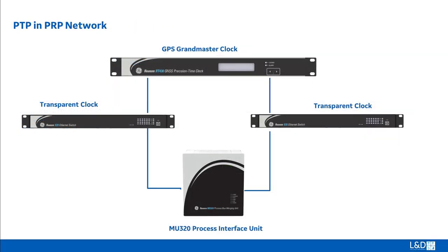Scenarios where using PTP in a PRP network is required are rapidly increasing, as these 2 protocols meet all the benefits and economical viability of using an Ethernet communication network to interconnect intelligent electronic devices, IEDs, inside the substation control house. It is indeed possible to achieve full redundancy with zero-time recovery when putting PTP and PRP protocols together.